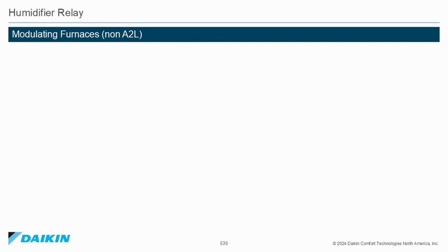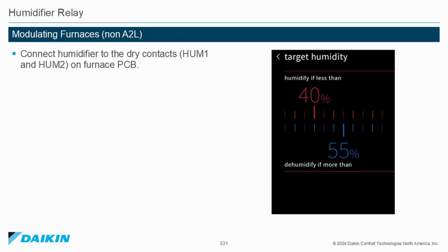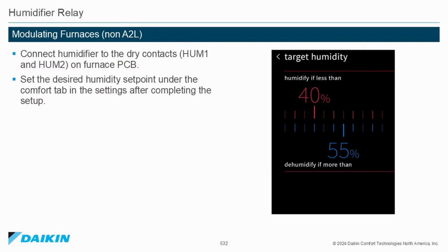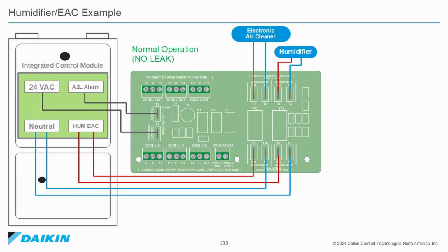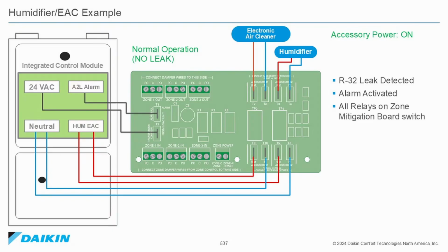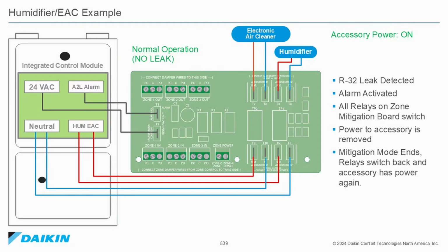On modulating furnaces, non-A2L, connect the humidifier to the dry contacts HUM1 and HUM2 on the furnace printed circuit board. Set the desired humidity set point under the Comfort tab in the settings after completing the setup. Here is an example of a humidifier and electronic air cleaner connections. Accessory power on, R32 leak detected, alarm activated, all relays on zone mitigation board switch, power to accessories is removed, mitigation mode ends, relays switch back and accessory has power again.